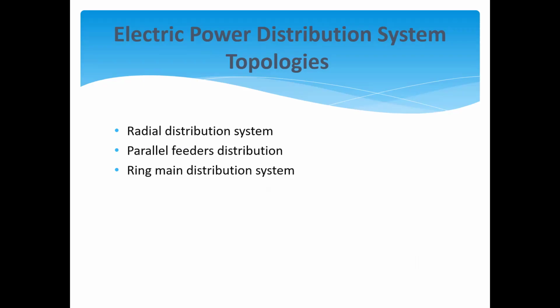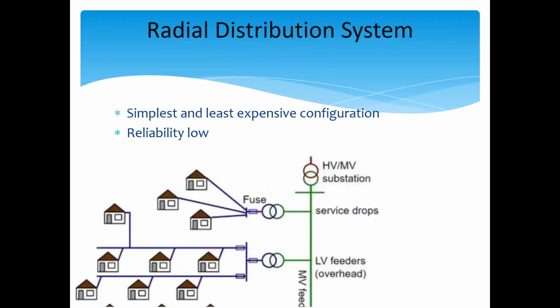Electricity power distribution system topologies also I want to show you in this section. There are 3 different distribution system topologies: radial distribution system topology, parallel feeder distribution topology, and ring main distribution system topology. Radial distribution system topology is the least expensive one, but its reliability is low. For example, if something happens in this section or here, the power to these consumers will not be delivered. So its reliability is low, but it's less expensive and simple.